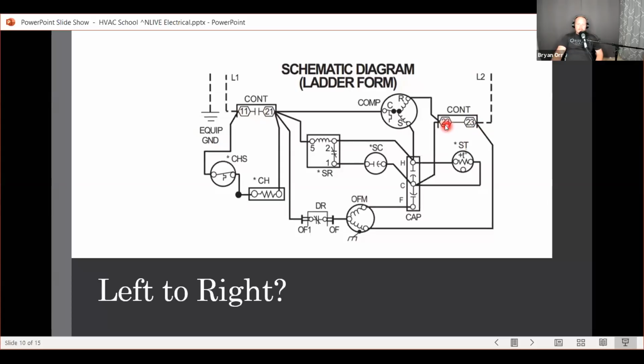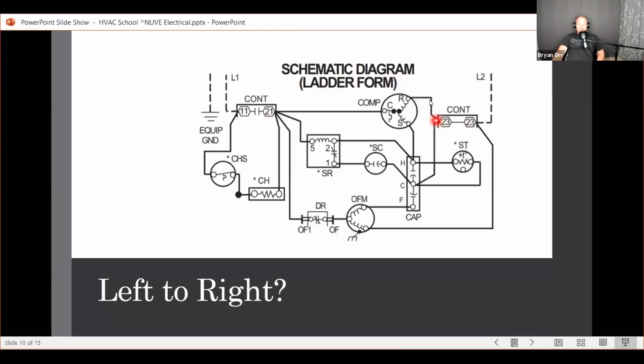So that's why it says 23 and 23, because electrically, these are the same points, which means that if you have this sort of system, you have L2 connected all the time. So L2 is connected all the time, which means that there is potential present everywhere in the circuit at all times, even when the system is off. But which side is that coming from? It's not coming from this side. It's not coming from left to right, because if we think just in terms of left to right, well, there, we got an open contact right there. No, it's coming from right to left, because this is the other side of the circuit.